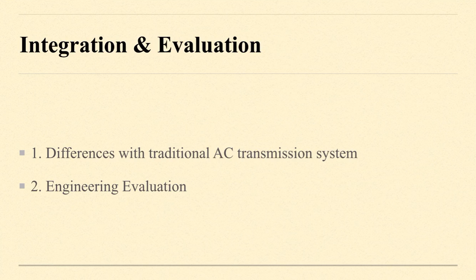Here is integration and evaluation. First is differences with traditional AC transmission system. There are many differences, including major installation, device status, power flow control, and so forth. And next is engineering evaluation. MMC converters hold the ability of dynamic independent and fast regulation of active and reactive power flow distribution. That is, reactive power compensation devices do not need to be equipped in MMC converter stations. Thus, MMC HVDC transmission projects would cover a much smaller area than that of traditional AC transmission projects.